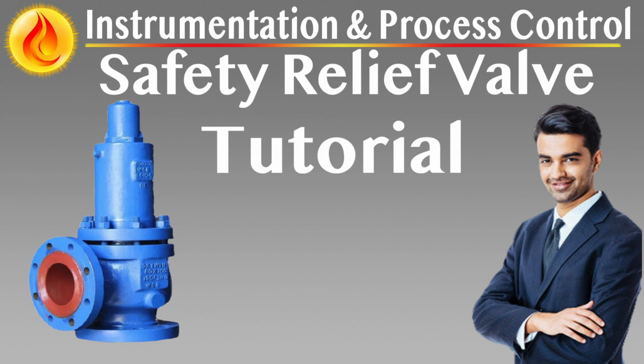General design and material standards. All relief valves must conform to internationally recognized codes. API 526 for flanged steel pressure relief valves, ASME Section 1 for power boiler service, ASME Section 4 for heating boiler service, ASME Section 8 for unfired pressure vessels.